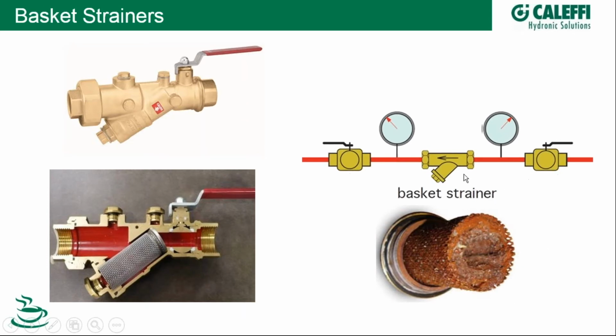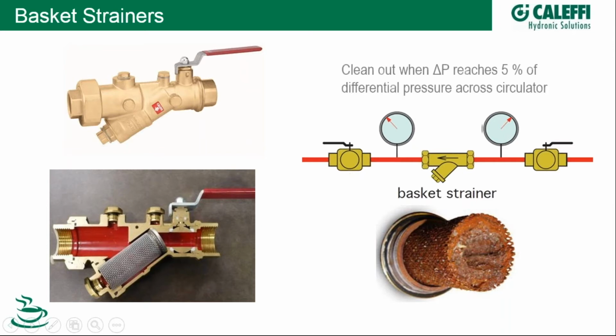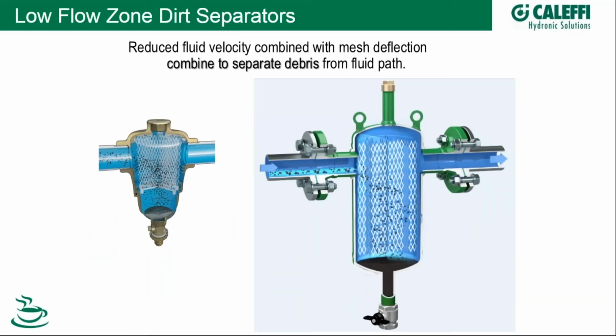It's always wise to isolate your Y strainers with ball valves if you're going to use them. Put pressure gauges on either side and monitor your pressure drop across the Y strainer. When do you change them out? Well, we recommend that if you don't have any other criteria, take the differential pressure of the circulator driving flow through that Y strainer, let's call it 10 feet of head, and at 5% of that value, in this case half a foot of head, you would need to change it out. Then you'd close the ball valves off and clean it out. That's how you would do basket strainers. So they have their purpose. We like them not so much down in the mechanical room, where you might find a device like the one in front of you now, but more up in fan coils and up high, where you don't have quite as much of an issue with debris.